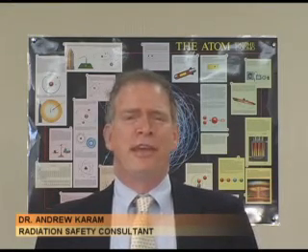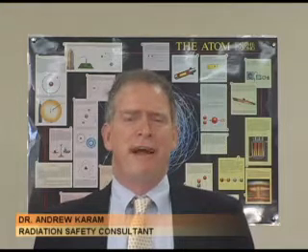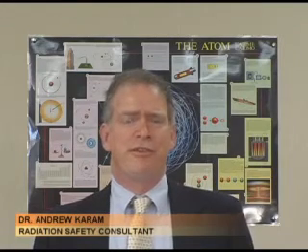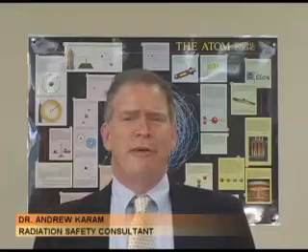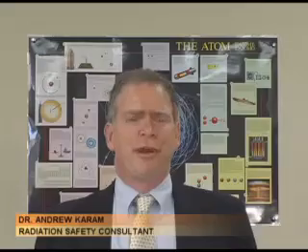Radiation producing equipment is treated differently in the regulations from radioactive materials. If you have a device, it's something that can be turned on or off and the radiation does not come out when the device is off. These are typically registered with the state as devices. Radioactive materials can't be turned off — a cobalt-60 source will always be radioactive. Radioactive materials are licensed by the state and are generally controlled much more stringently. What I'm going to be talking about in this talk are the x-ray generating devices, not the materials themselves.